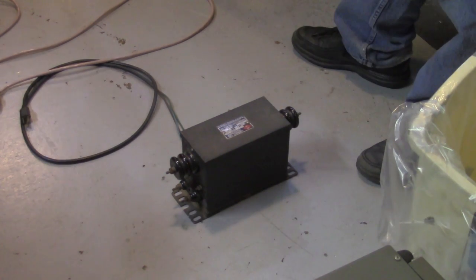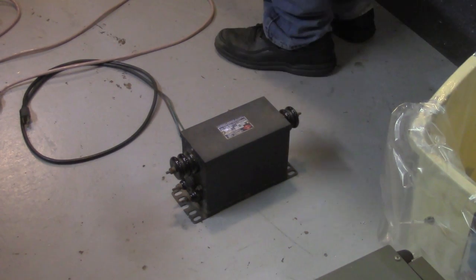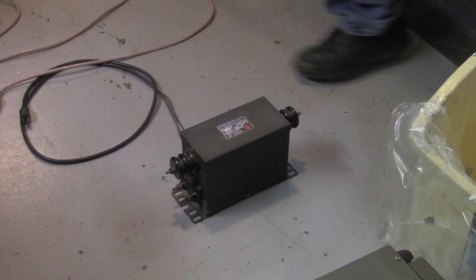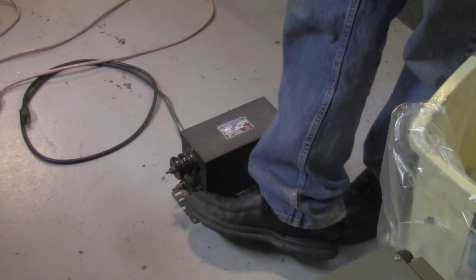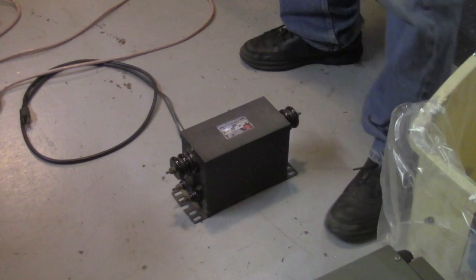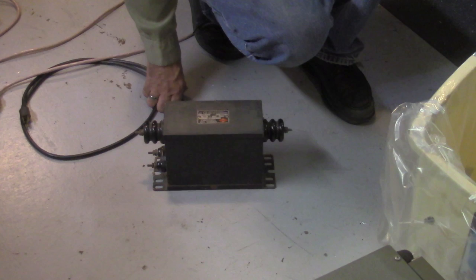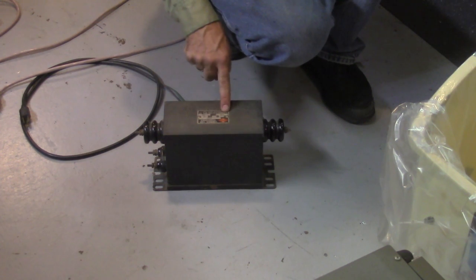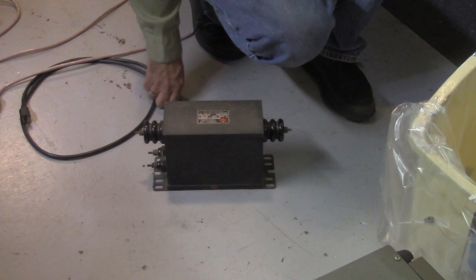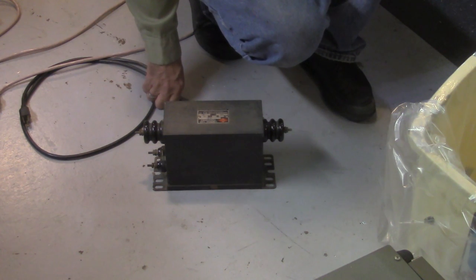He's not here to defend himself. We got this in with some other junk. I don't know how we get forced into these things. Anyway, it needs testing and I checked it with a voltmeter. It's the ohmmeter. That's the primary down here. This rather formidable looking insulators are the secondary. This is six thousand volts and 115.